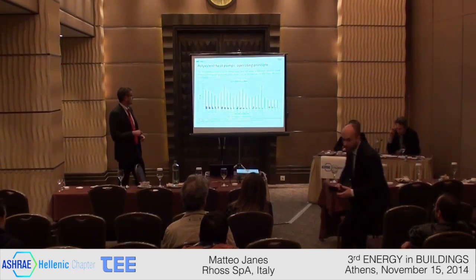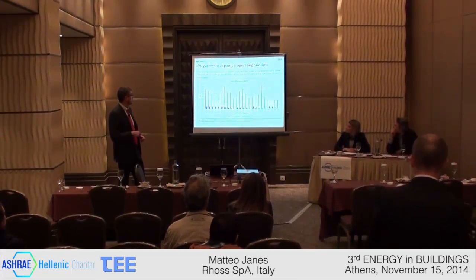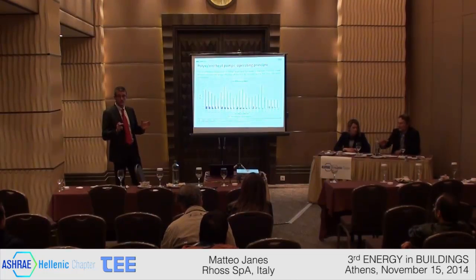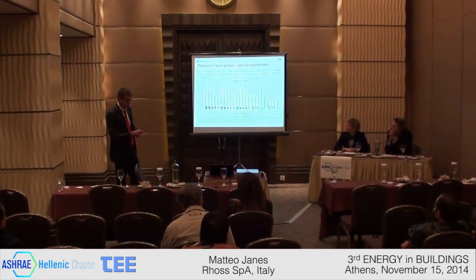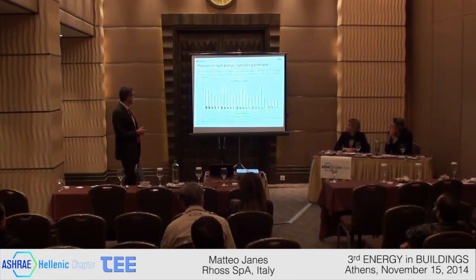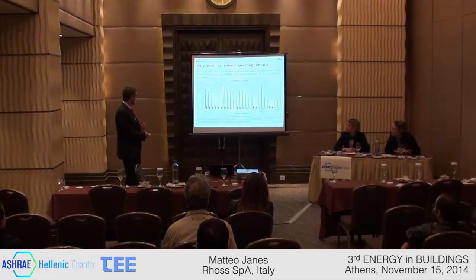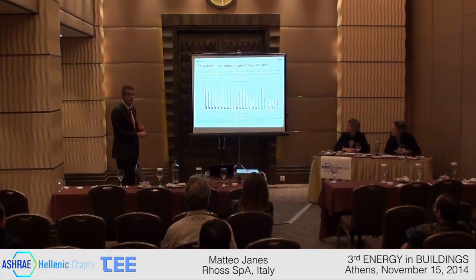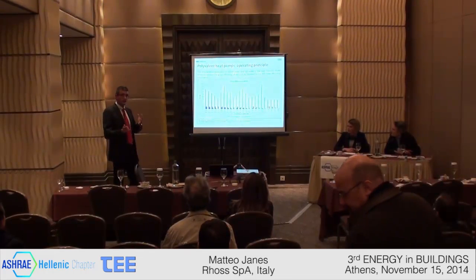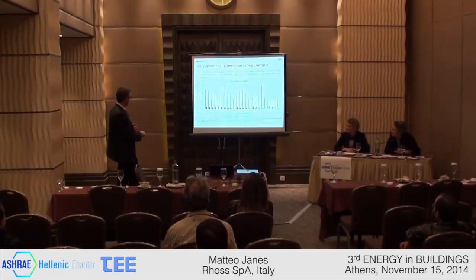So the manufacturers and insiders use the TER, total efficiency ratio value, which is the ratio between the sum of cooling and heating capacity in specific operating conditions and the power input used to obtain this. This is the typical trend of a TER value for a polyvalent heat pump, let's say rated at 550 kilowatts, working in a mid-season situation, so 15 Celsius ambient temperature, producing chilled water at 7 and hot water at 45 Celsius. We can see that when the cooling and heating loads are comparable, so both 100%, both 75, 50 or 25%, the TER value reaches its best values.